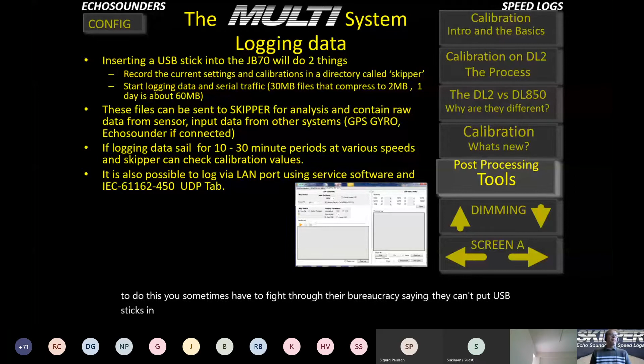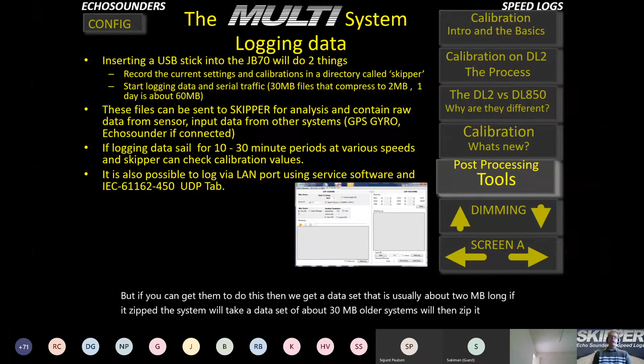So, logging data. Whenever you're doing a calibration or a sea test, or you've got a problem, the first thing we ask is for the vessel to put a USB stick in. You don't have to be present for them to do this. You sometimes have to fight through their bureaucracy saying they can't put USB sticks in the system. But if you can get them to do this, then we get a data set that is usually about 2 megabytes long. If it's zipped, the system will take a data set of about 30 megabytes. Older systems will then zip it automatically. The newer softwares won't zip it. The customer has to do that.